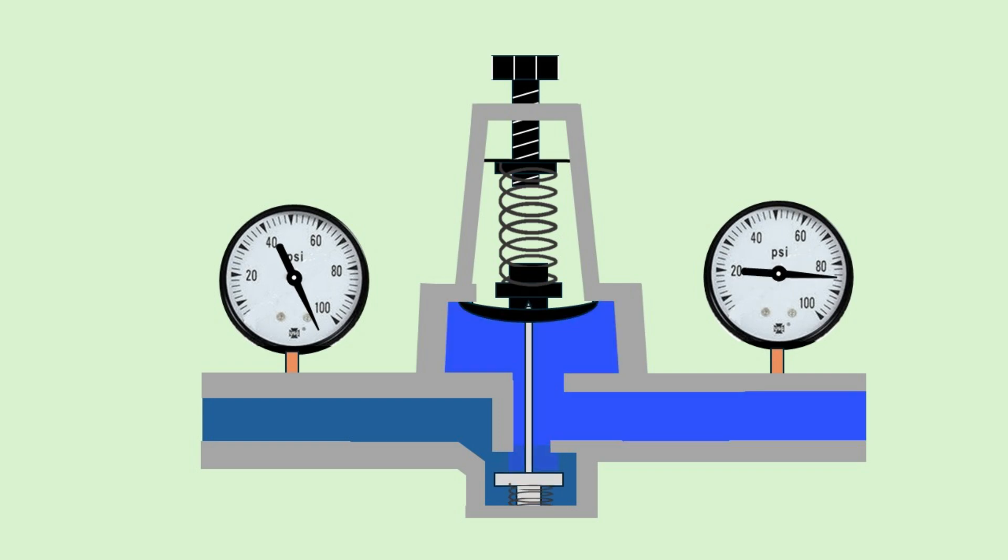When the gap widens, there is a smaller pressure drop, so the outlet pressure increases. When the gap narrows, there's a larger pressure drop and the outlet pressure decreases.